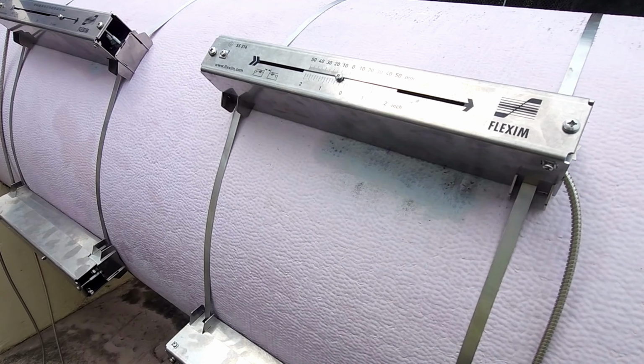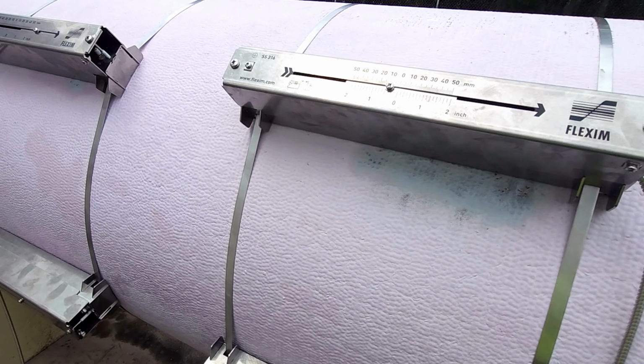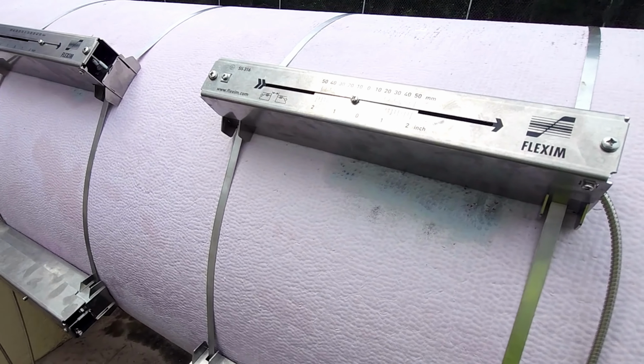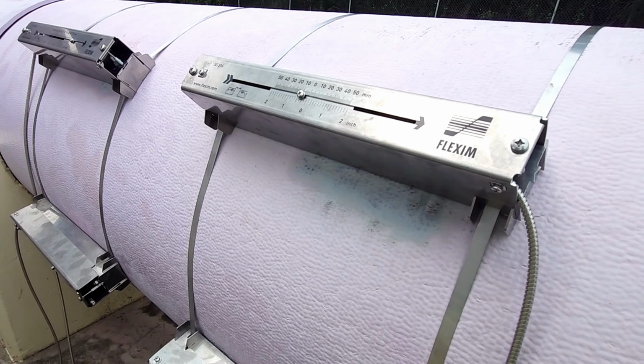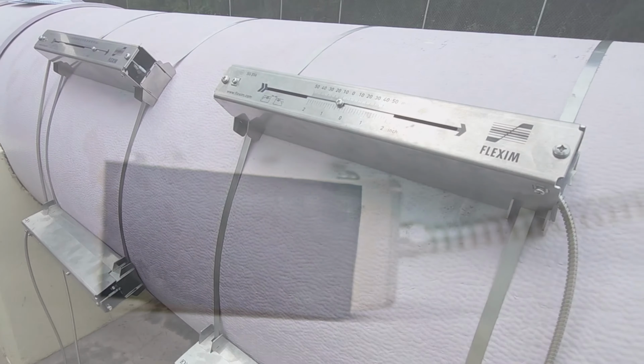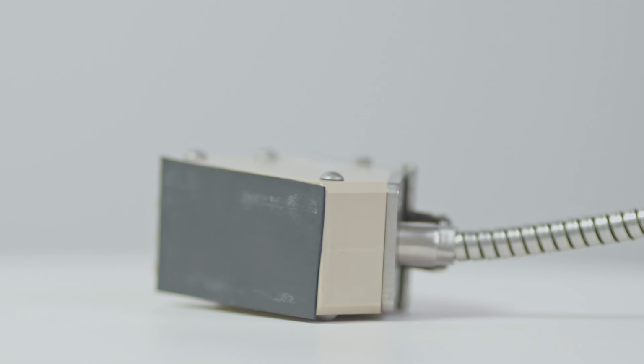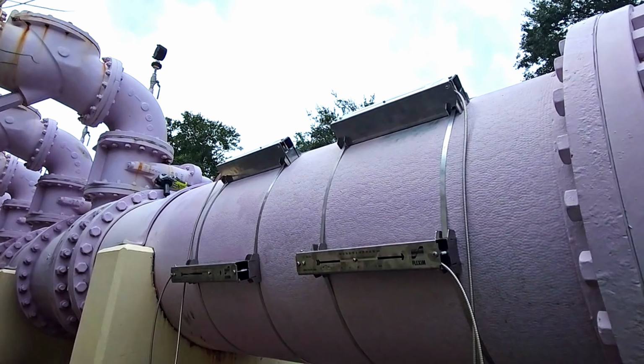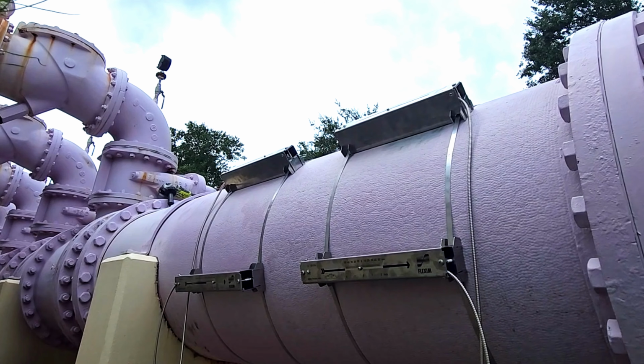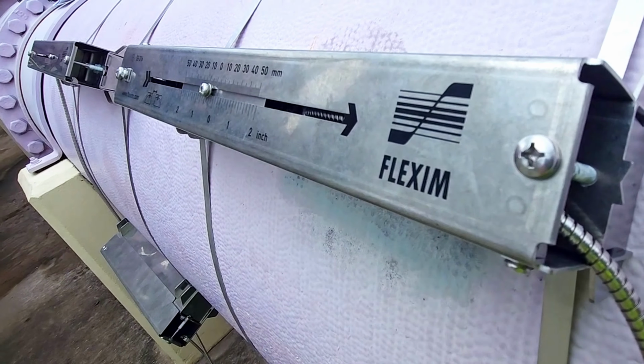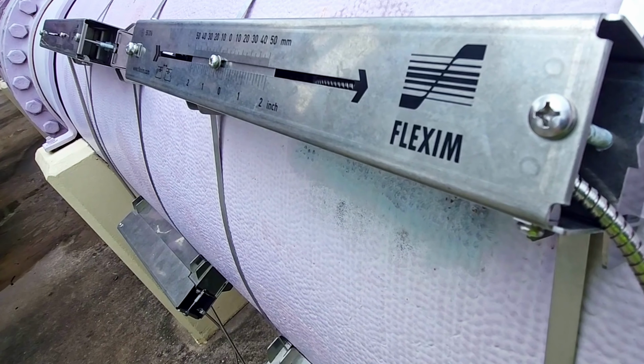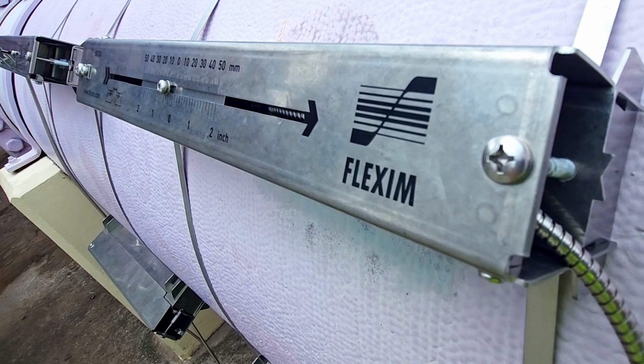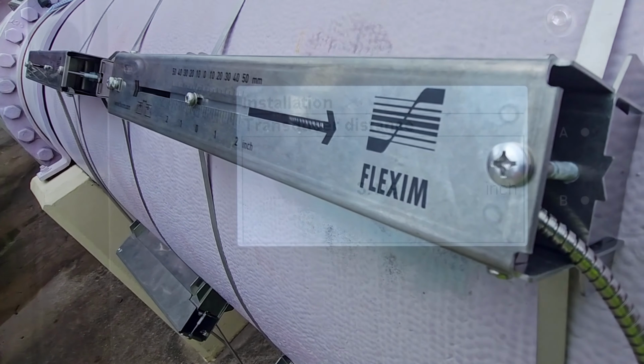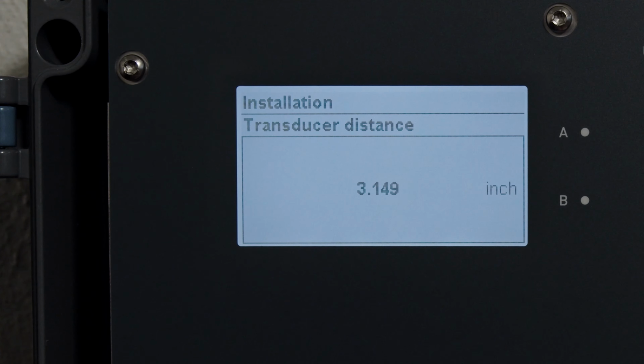Secure the necessary robust sensor hardware to the pipe with the included quick and straightforward mounting hardware and steel band kit. Use the included Viton solid coupling pads. Measure the distance between the transducers, matching the separation provided by the meter transmitter. Complete the meter installation by closing and securing all parts of the transducer mounting hardware and confirming the transducer separation distance on the meter transmitter.